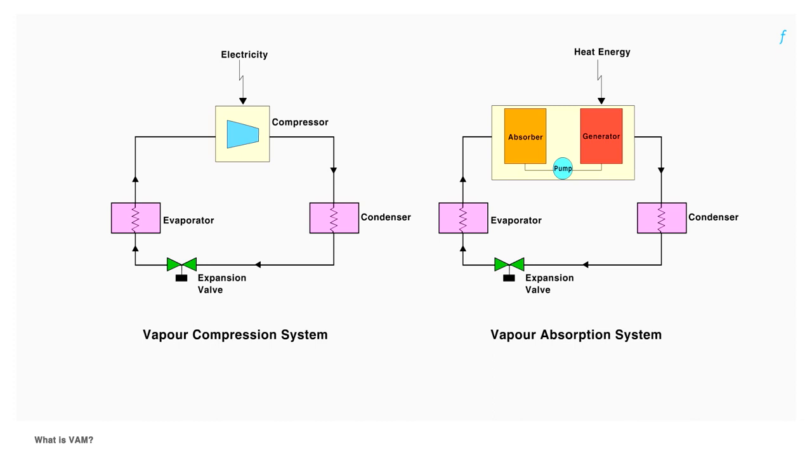Conventional air conditioning systems are mostly vapor compression machines. VAM is similar to these systems but has two distinguishing elements. First, VAM doesn't use a compressor which is the most energy intensive component of any refrigeration system. This is replaced by an absorber generator unit. Secondly, VAM is powered by heat energy compared to vapor compression machines which are powered by electrical energy.